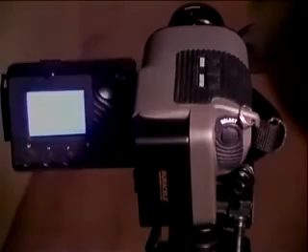Next, use the select button to move to level on the camera control menu. The adjust button now adjusts the level of both the camera's external video output and the brightness of the viewfinder display — plus for brighter, minus for darker. Practicing the adjustment possibilities of the Palm IR Pro will allow the operator to quickly learn which settings are best for existing conditions.